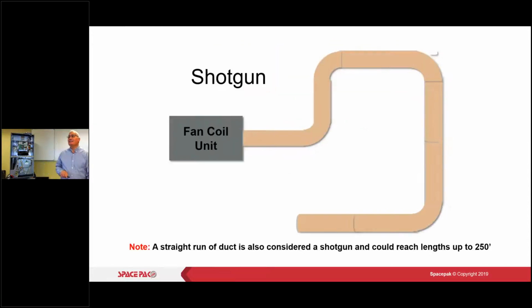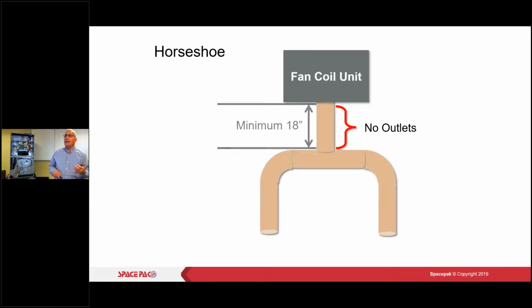So here's my shotgun approach. So maybe I got my fan coil in the middle of the attic here, and then I'm coming off, and then I'm hitting my elbow, and I'm trying to get my plenum to the edge of the attic space as much as I can and bring it back before I take my drops off. Horseshoe, I'm going to have that type of line up this way, 18 inches minimum before I hit my T, and never any outlets on that part of the plenum. So all outlets are going to happen after that T and after those elbows.